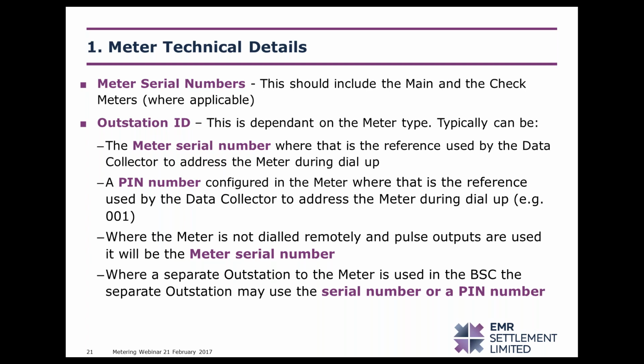Typically, this is the address used by a data collection system to be able to identify and communicate with that metering system. In a lot of modern meters, it is either the meter serial number itself or a unique PIN number used to identify that meter. Where the meter is not being dialed remotely and pulse outputs are to be used, for example, the meter serial number should be used. Where a separate outstation is used, you must include all relevant details for that outstation as well, as the outstation ID may be different from the meter outstation ID.